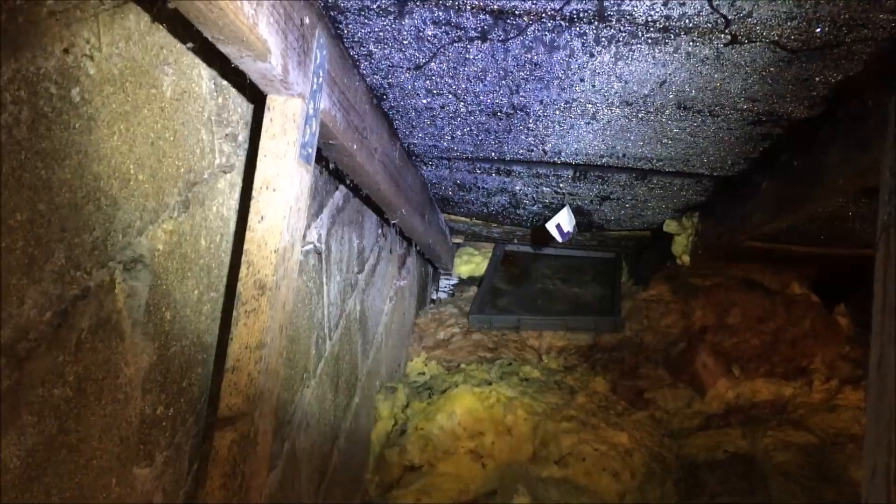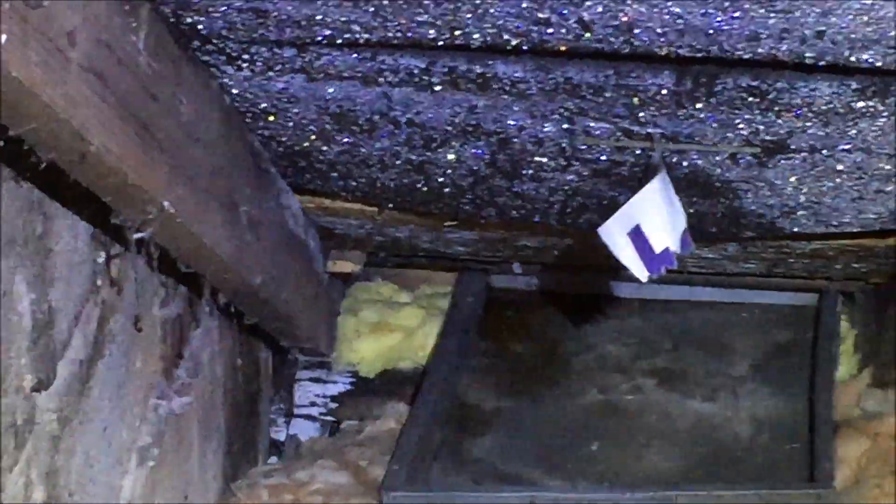We have a property here in Yorkshire and the roof has got severe condensation. As you can see looking down there, it's actually glistening — early signs of decay. Because it is severe condensation, it's very wet. If you look right here in the timbers, you can also see all the staining. Water's running down, literally dripping everywhere — it's terrible, falling all over me.